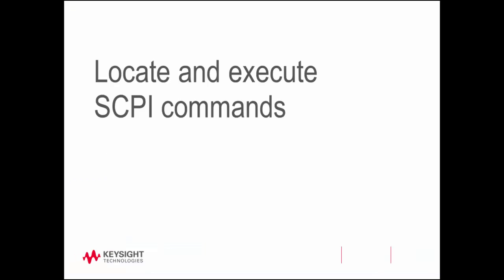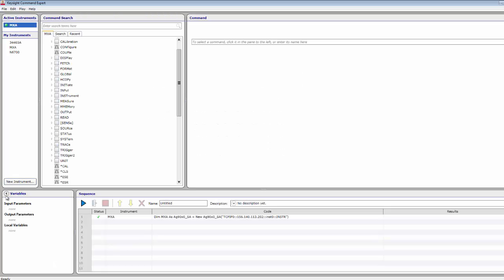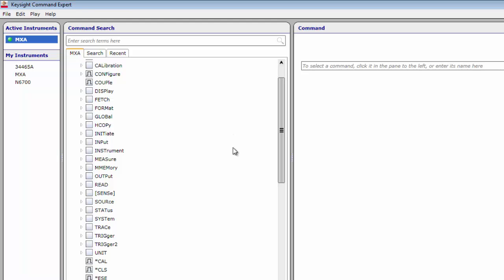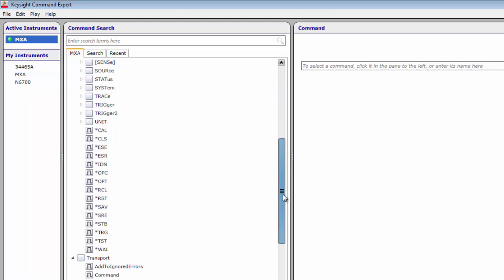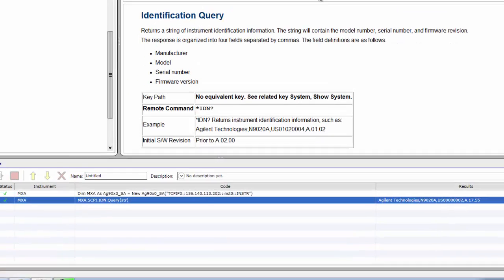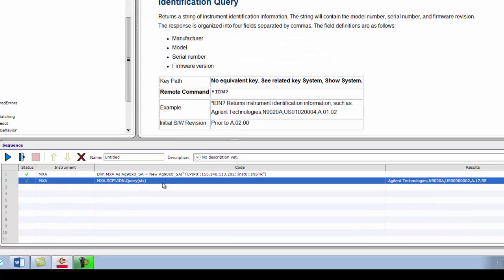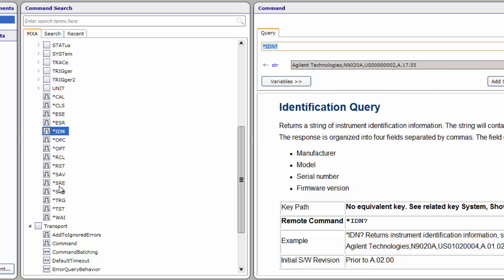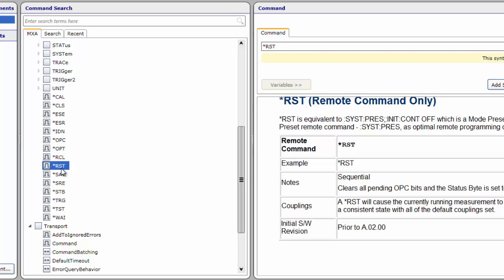Now let's locate and execute a few SCPI commands in the Command Set tree. In the Command Search pane, scroll down and select Star IDN in the Command tree. Star IDN provides instrument identification information including the instrument model, serial number, and firmware revision. Click the Add Step and Execute button in the Command pane to send the Star IDN query to the instrument. Command Expert displays the output of the query and adds a corresponding step to the Sequence pane. Next, let's reset the MXA to its power-on factory default state. Select Star RST from the Command tree and click the Add Step and Execute button.